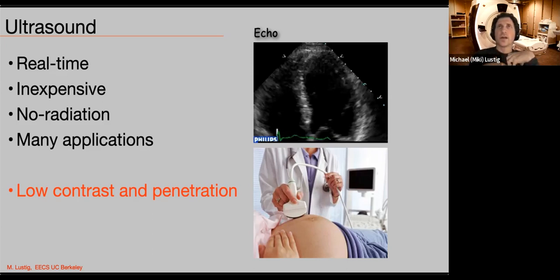When it's used in the heart, it's called echo. When it's used everywhere else, it's called ultrasound. Whatever, but that's what it is. The problem is it has a little bit low contrast. It only sees differences in acoustic impedance between tissues, so you get reflections coming back from those. And it doesn't have great penetration, and penetration actually depends on resolution. If you want higher resolution, you have to go to higher frequencies, but then you have more attenuation. So there are definitely trade-offs there.